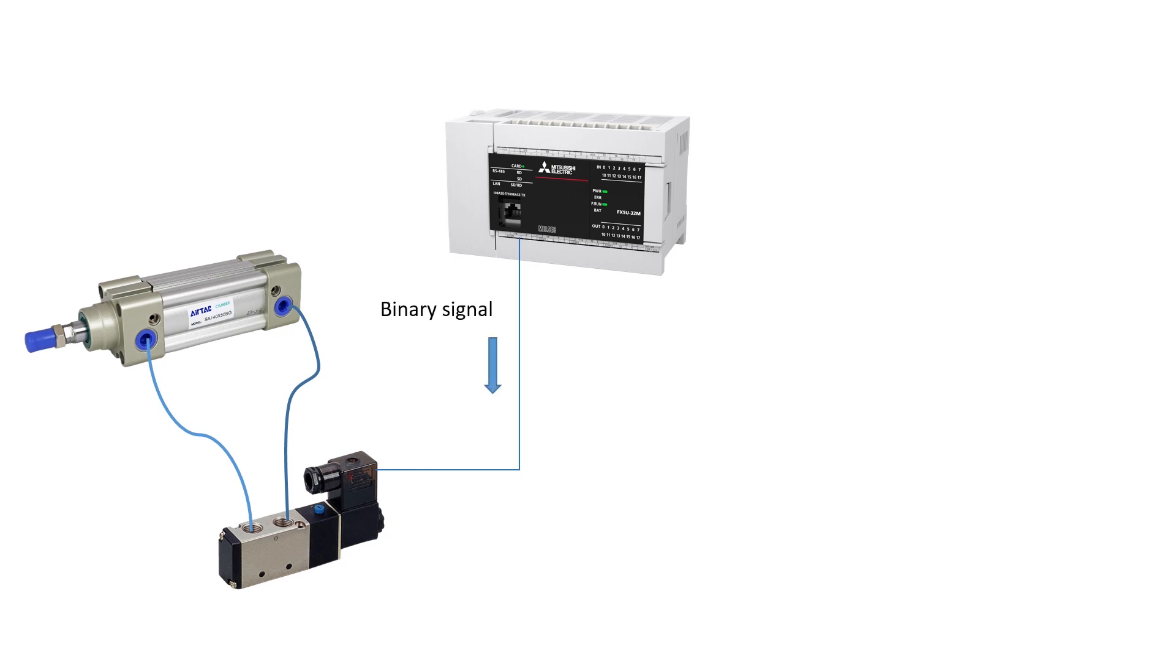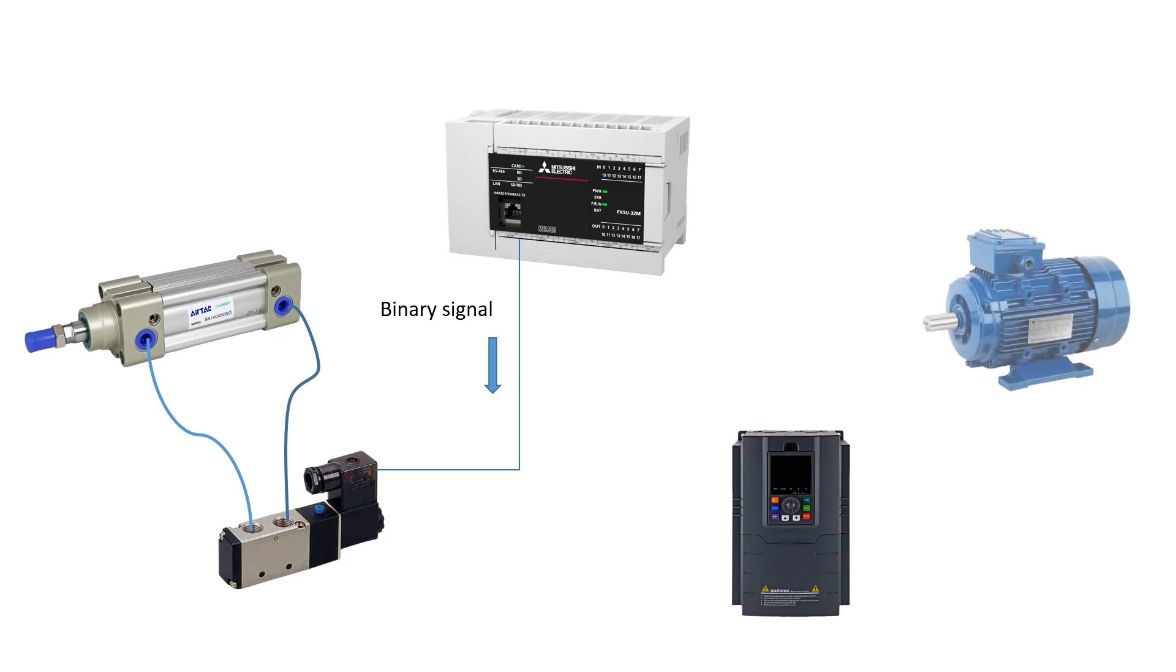One more example is operating an induction motor through a variable frequency drive. The VFD receives signals from the PLC to control the speed of an AC motor by varying the frequency and voltage supplied. Here, the PLC sends an analog signal to the VFD to regulate the motor speed based on the application's control requirements.